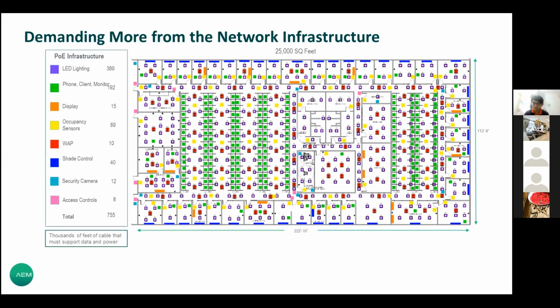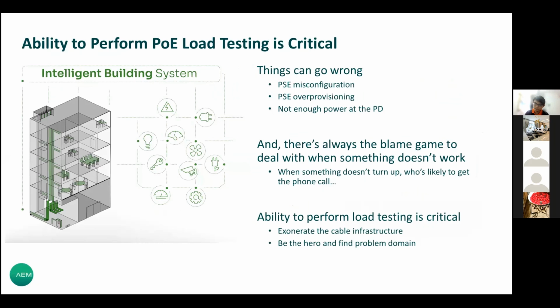Besides cable certification, you have to make sure the signal is not affected by noise, and that the PoE can run. It's a lot now, just looking at cable—it's no longer just pass return loss, pass crosstalk, pass connectivity, no breakage, good enough. That's no longer enough. You have to consider all these factors.